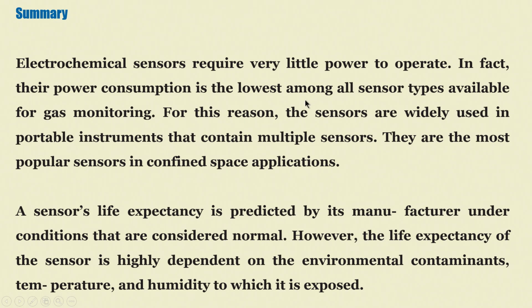Their power consumption is the lowest among all the sensor types available, and for this reason they are widely used in most of the portable instruments that contain multiple sensors. They are the most popular sensors in confined space applications. A sensor's life expectancy is normally predicted by its manufacturer under specified conditions.